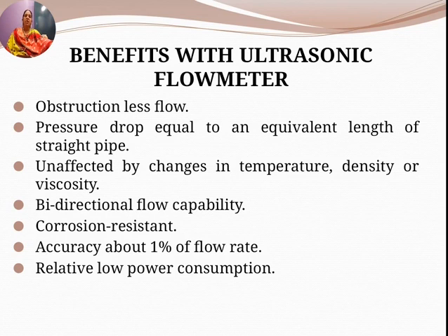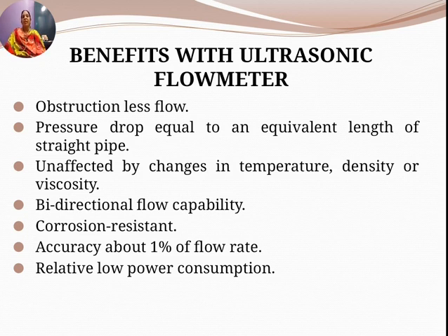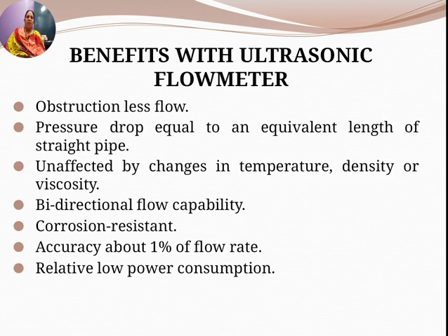Benefits of ultrasonic flow meters: they are obstruction-less; pressure drop equals that of an equivalent length of straight pipe; unaffected by changes in temperature, density, or viscosity; have bidirectional flow capability; are corrosion resistant; with accuracy of about 1% of the flow rate; and have relatively low power consumption.